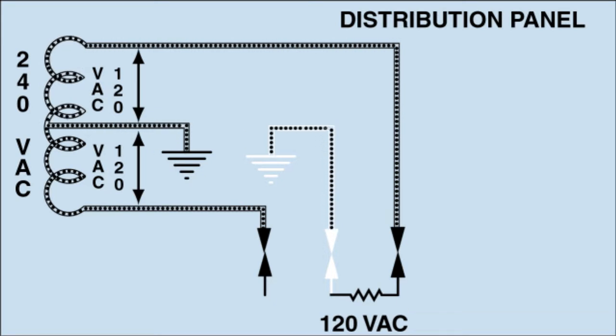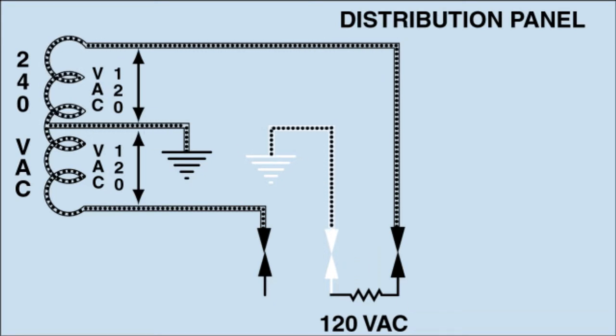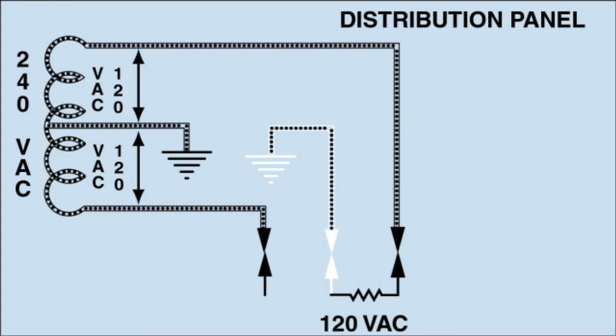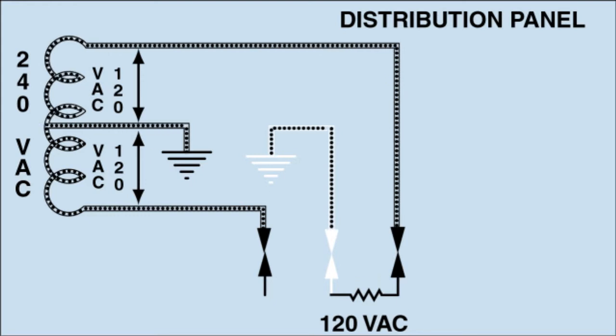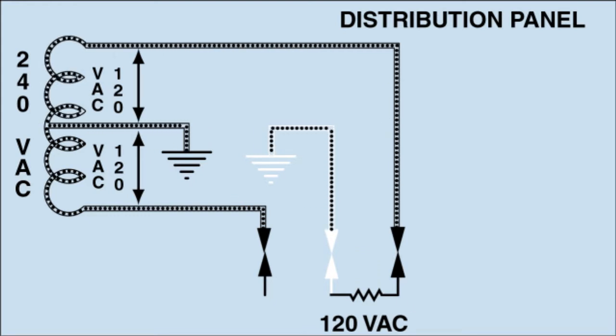Pause the video here if necessary to solidify this idea in your mind. A perfectly balanced distribution panel, which is much more theoretical than practical, will have no current flow in the neutral from the panel to the pole and therefore will waste no power.